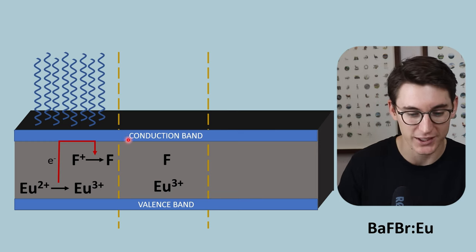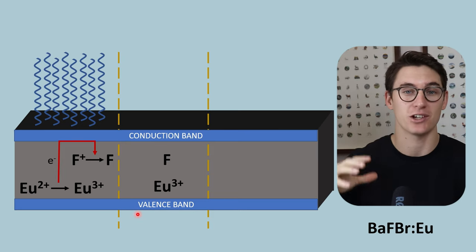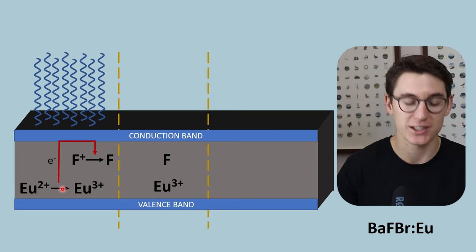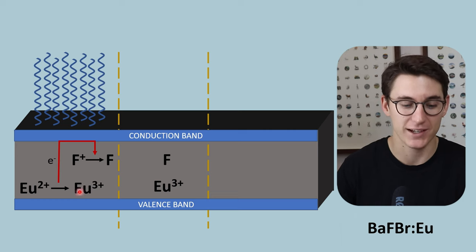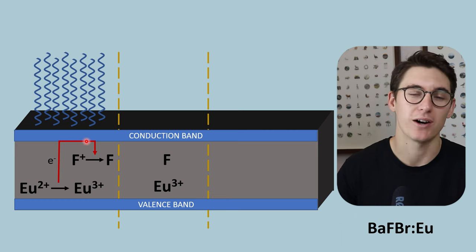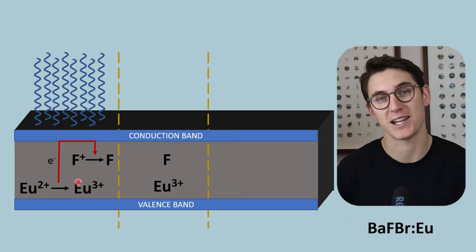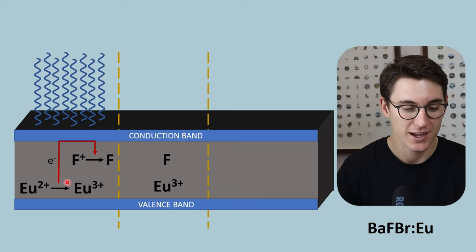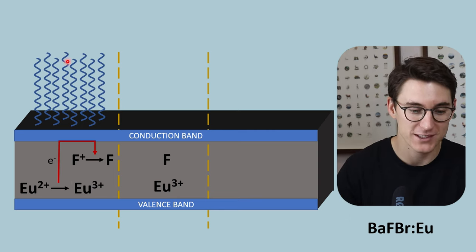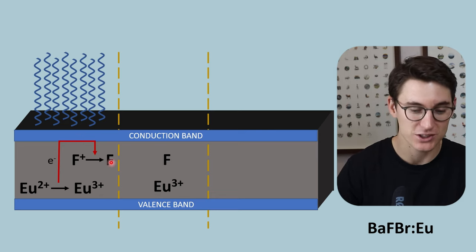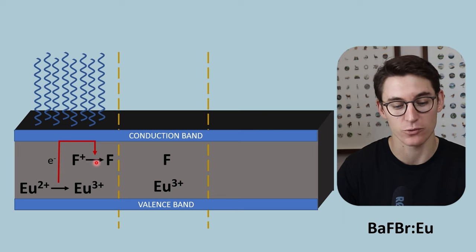When we expose this cassette to x-rays, energy is put into the system and electrons from our valence band are released to our conduction band. That release of electrons causes europium 2+ to be oxidized to europium 3+ — it has lost an electron. Oxidation is loss of an electron. That electron, which has gained energy from the x-rays, goes to the conduction band and falls into the F-centers — the positively charged fluoride atom has now gained an electron and been reduced.